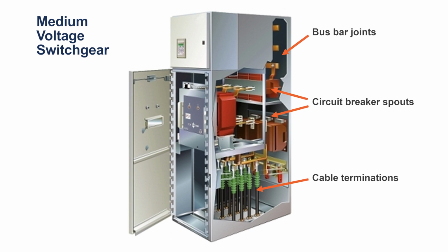So Elvis, if we have a look, medium voltage switchgear, what are the failure mechanisms? What is the risk? What is it that you see when you do the assessments? So basically, James, high voltage or medium voltage switchgear has been identified as one of the critical assets that companies look at when they analyze operation risk at their facilities. And partial discharge has been identified as a cause of about 85% of failures or faults of switchgear.